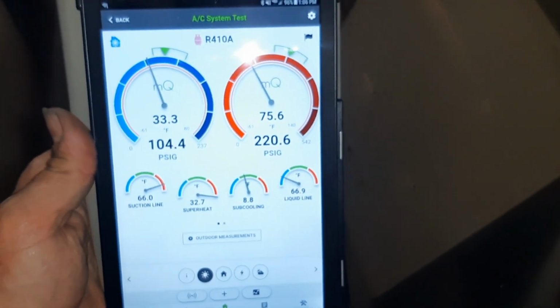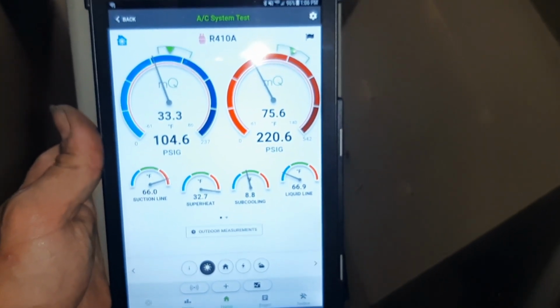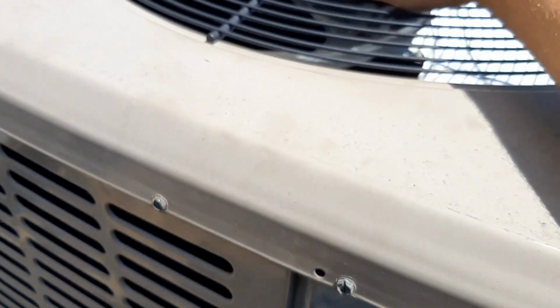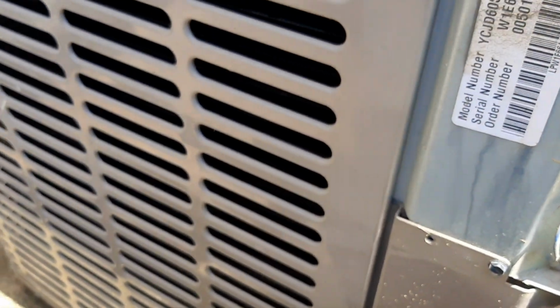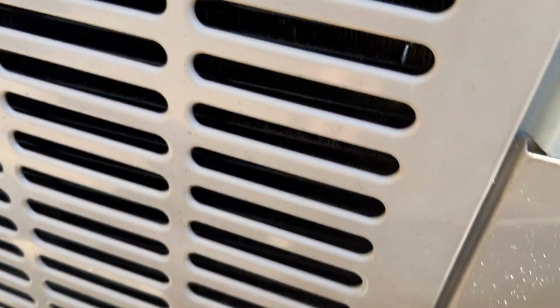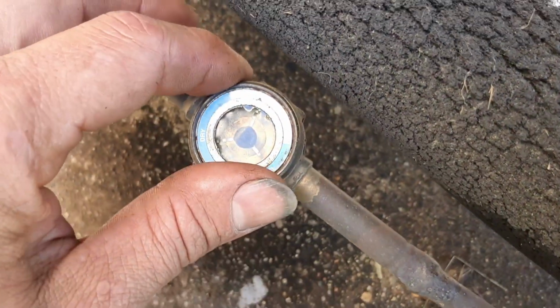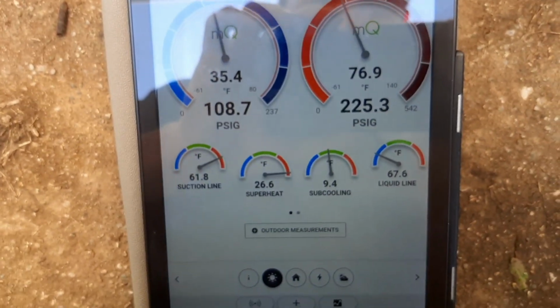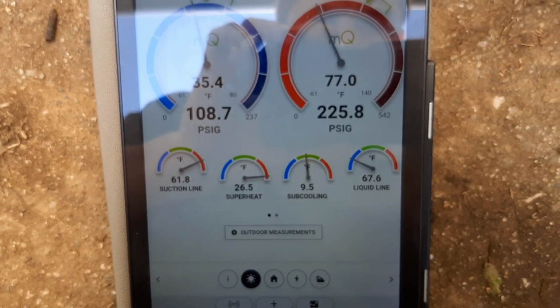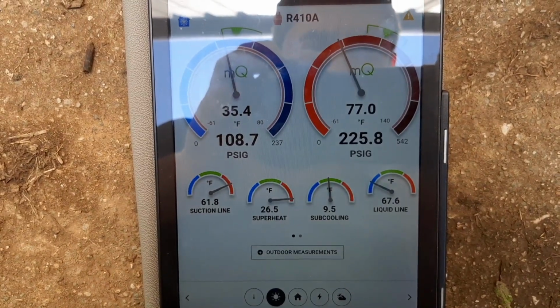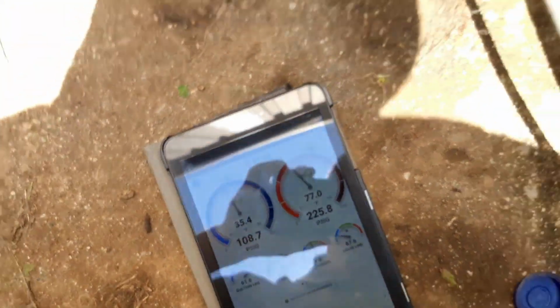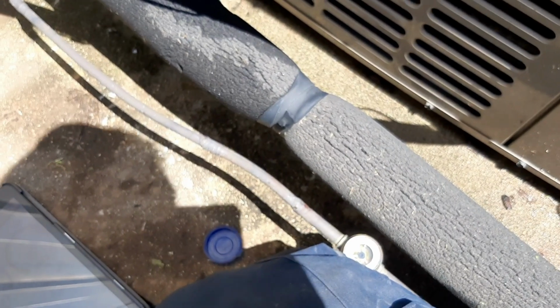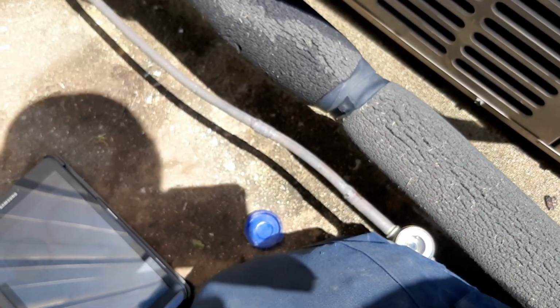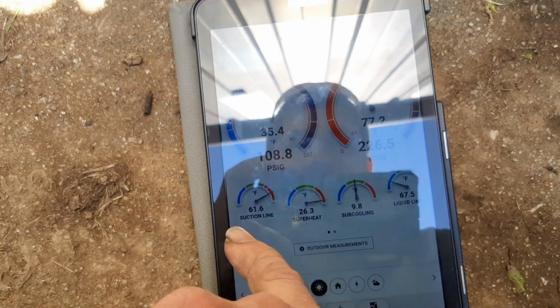So we're gonna let it run for a little while, see where we're at. I am getting a little heat out of it. My coil's probably still a little wet. Sight glass is clear. Superheat came down, still kind of dropping. Subcooling's in range. I mean, it doesn't look perfect, but again, we know what we got, so it's not really going to be perfect. As long as my superheat gets within range, I'll be happy with it.